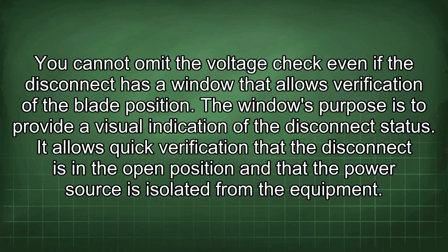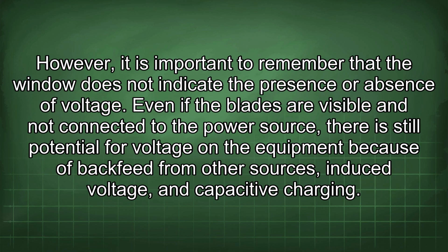You cannot omit the voltage check even if the disconnect has a window that allows verification of the blade position. The window's purpose is to provide a visual indication of the disconnect status. It allows quick verification that the disconnect is in the open position and that the power source is isolated from the equipment. However, it is important to remember that the window does not indicate the presence or absence of voltage.